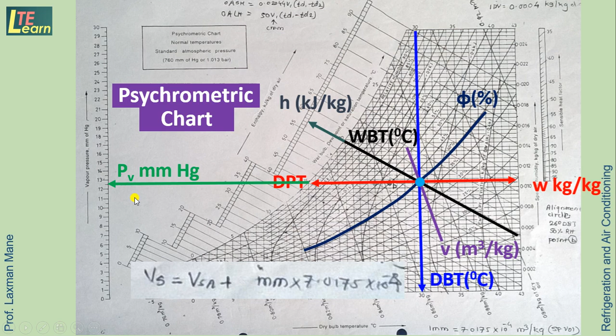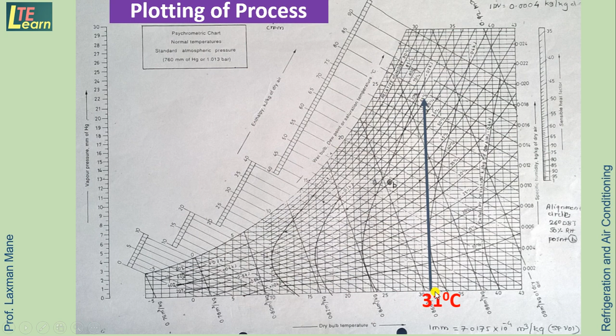So for that we need a set of temperatures at inlet and outlet. At inlet, take the dry bulb temperature. From the dry bulb temperature value on the chart, draw the vertical line, project the vertical line in this way. This is the wet bulb temperature, project the WBT line parallel to the WBT lines. Intersection point, this is point number 1.